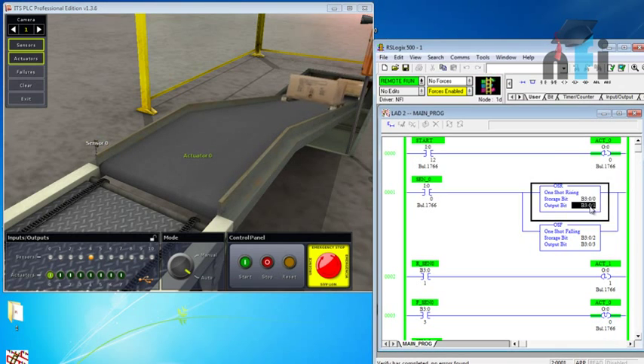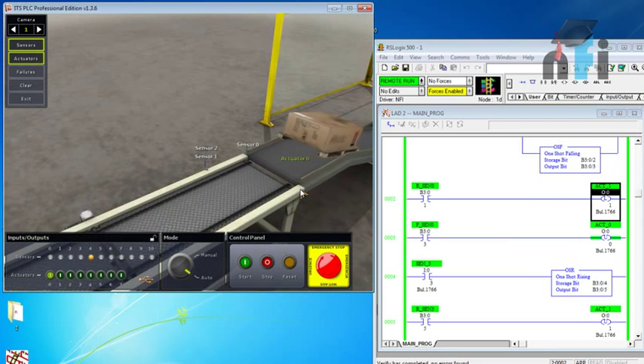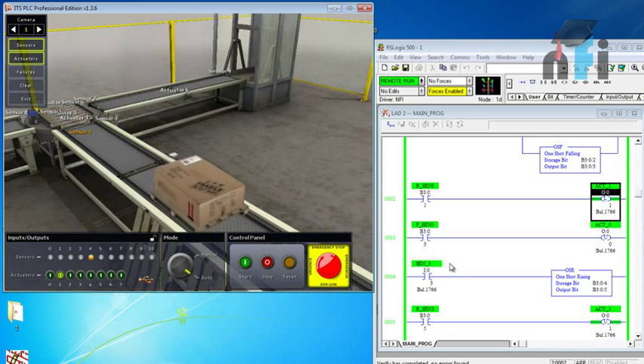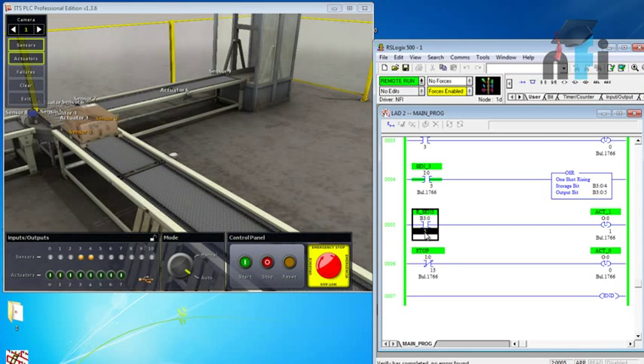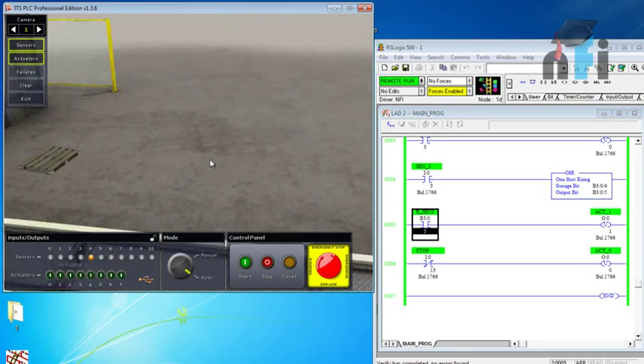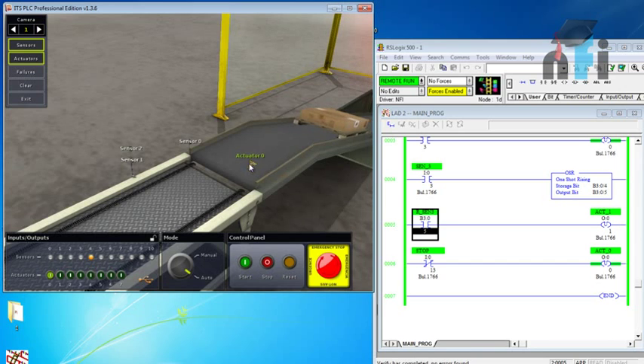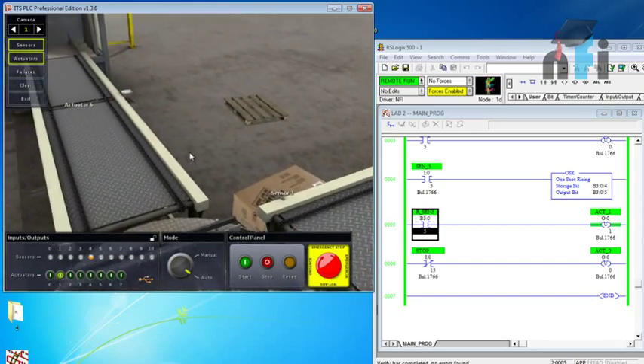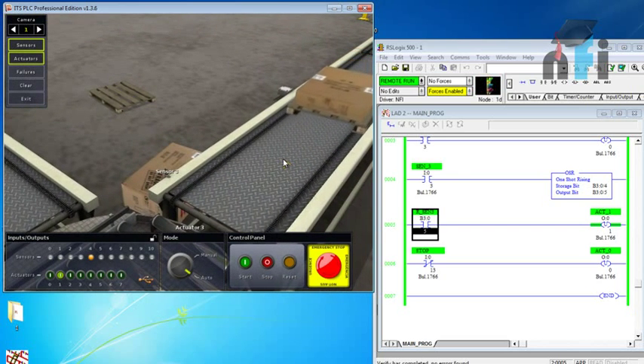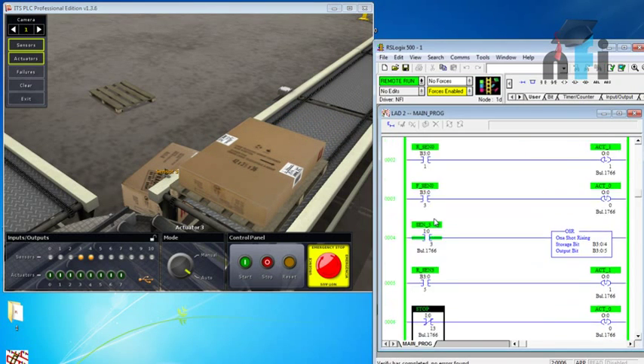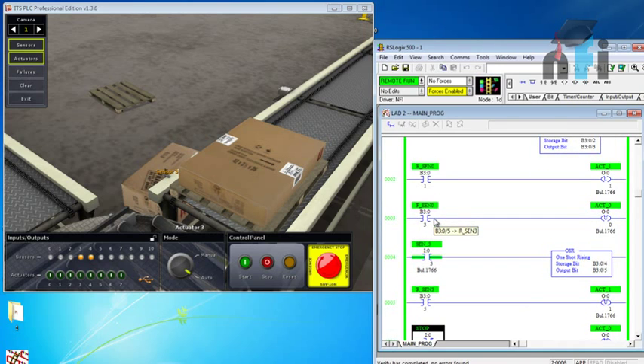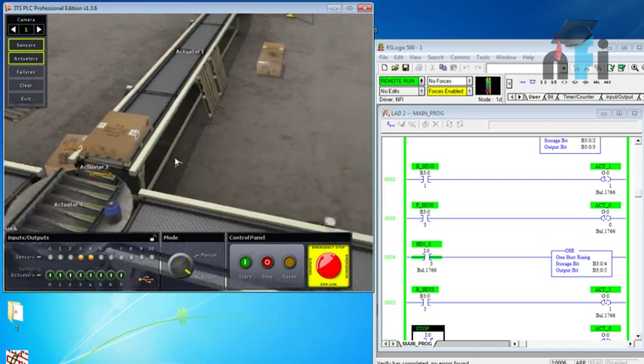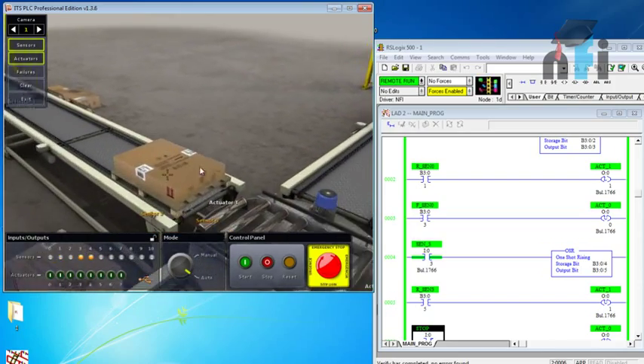Sensor zero gives the rising edge of this one which will latch actuator one. When the box leaves, actuator zero stops and it moves forward until it reaches sensor three, then this conveyor will be off with the rising edge. So that's how you can program the PLC using rising edge and falling edge, using NO contact and latch and unlatch commands to bring the box from one location to another. Further, we'll be delivering this box to a roller conveyor, rotating it, and delivering to another side conveyor - let's do that in the next videos.